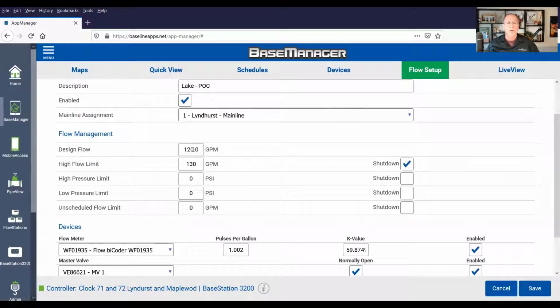The first thing we notice is that there's a design flow of 120 GPM set. That's good. The high flow limit is set for 130 GPM, and they've clicked shutdown. If shutdown is not selected, what would happen is if it's flowing higher than the 130 high flow limit, it won't shut down. That's obvious, but it will send an alert. Shutdown is always a good idea for high flow limit because it's probably a catastrophic mainline failure, and I want to have that shut down. If there were pressure limits, you'd want those set here and decide if you want to shut down or just get an alert.